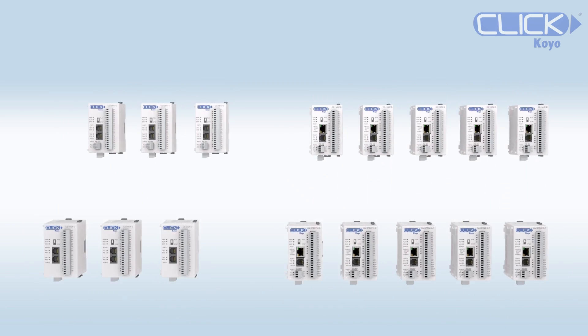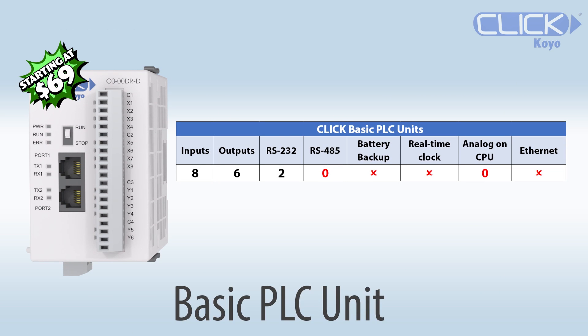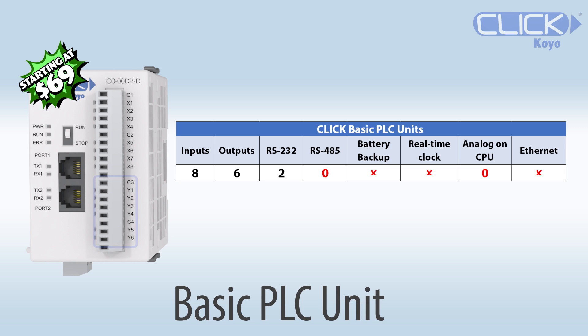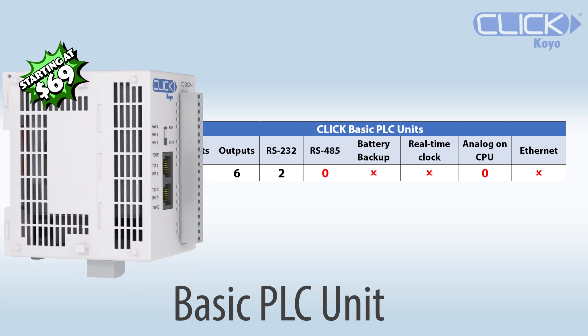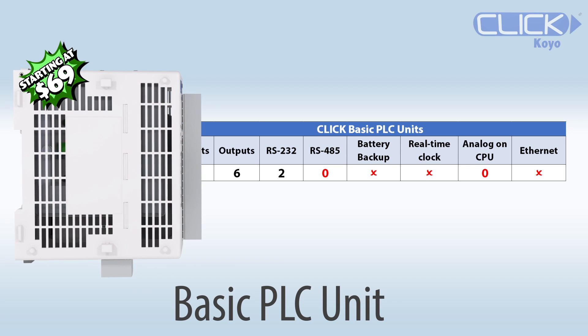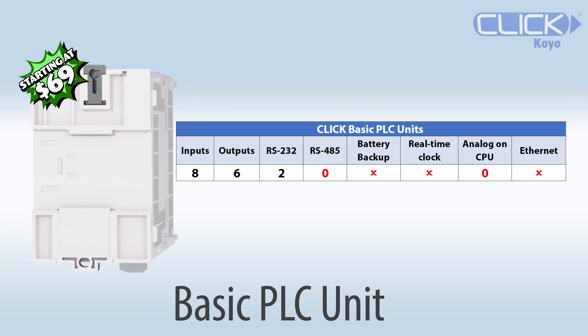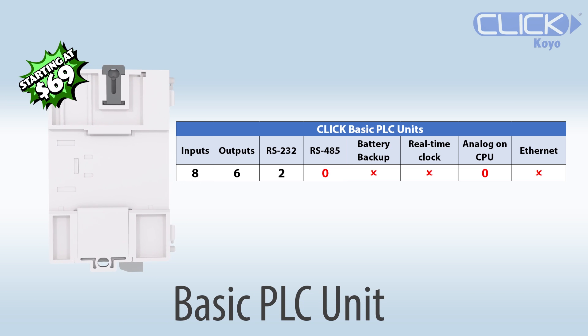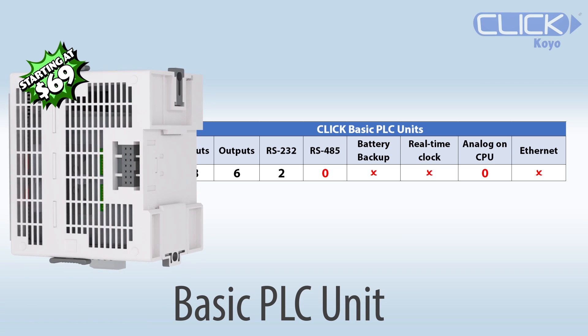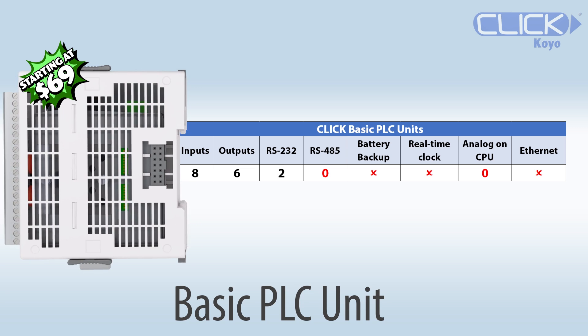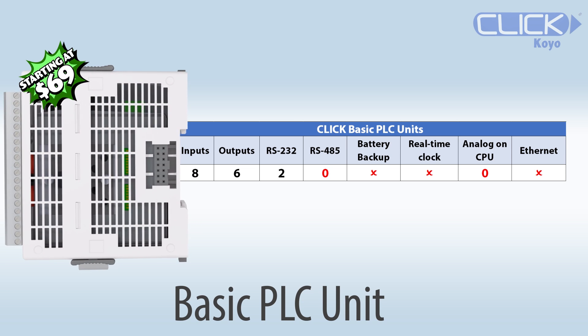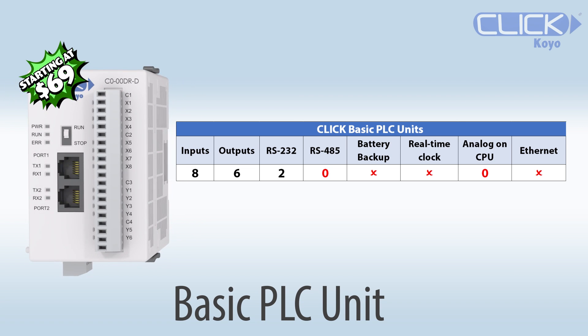Under Serial Only, there is the Basic PLC that has 8 discrete inputs and 6 discrete outputs on the CPU, with 2 serial ports. This unit does not have a battery backup. Not having a battery backup means that the values in your memory addresses will not be retained in the event of a power loss. Your PLC program will be retained on a power loss as it is stored in EEPROM.